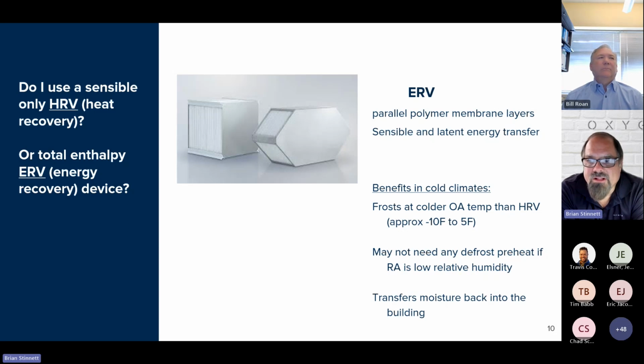So in Denver climate, depending upon how much moisture there is in the exhaust air, I may not need to run a preheater at all. So I can eliminate all that preheat energy that I would have to have with that aluminum HRV. The other benefit too with an ERV is that it helps to transfer moisture that's in that exhaust air back into the building during the winter.